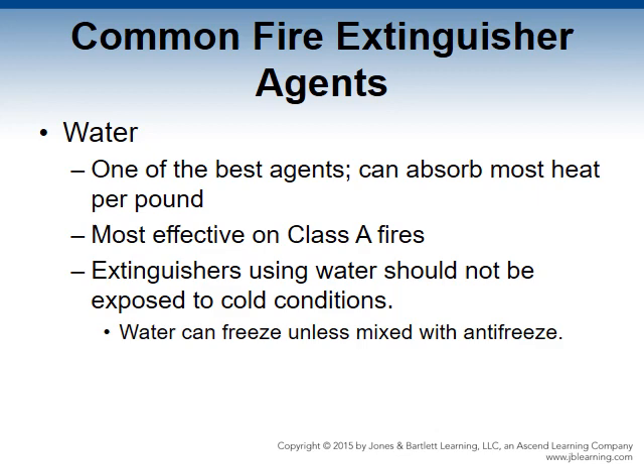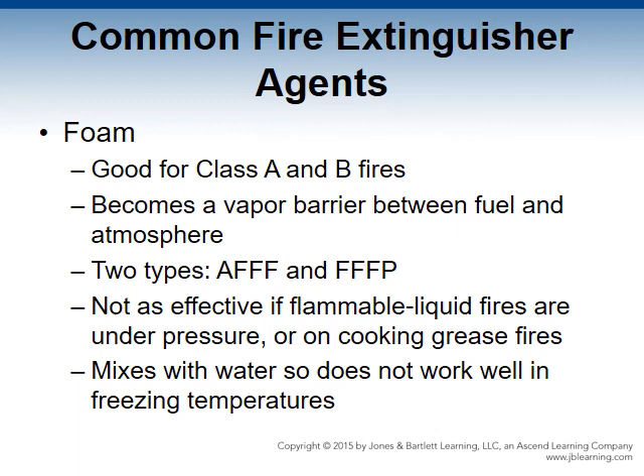Water is one of our best agents because it can absorb more heat per pound than any other known material. It is most effective on Class A fires but not effective on some fuels and dangerous with others. Extinguishers using water must be located away from cold conditions as water can freeze and render the extinguisher useless, unless mixed with antifreeze — though at certain ratios, antifreeze mixtures can be flammable.